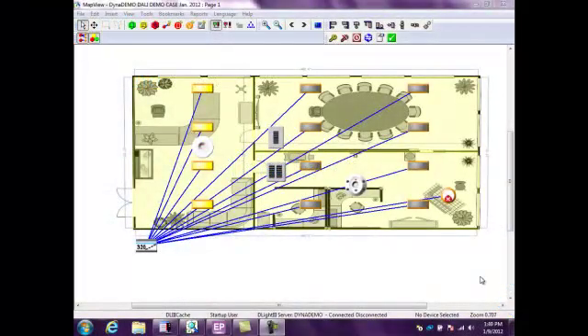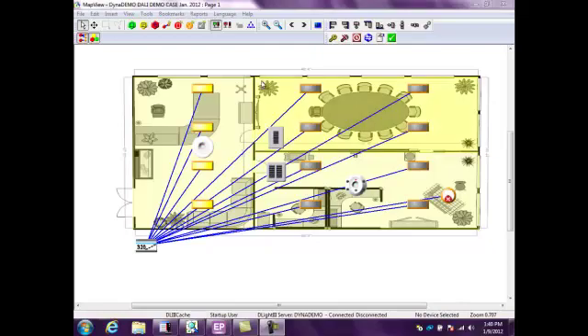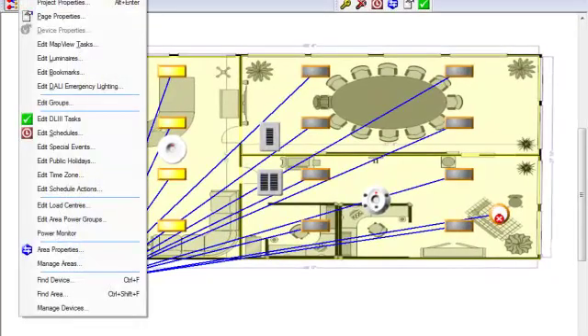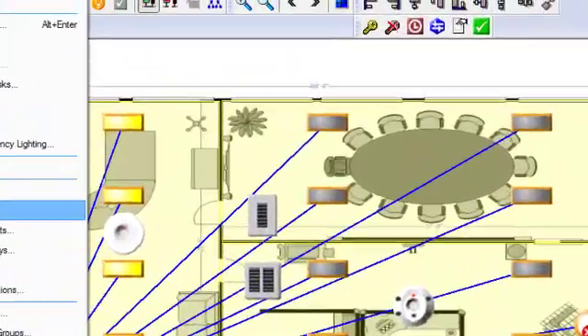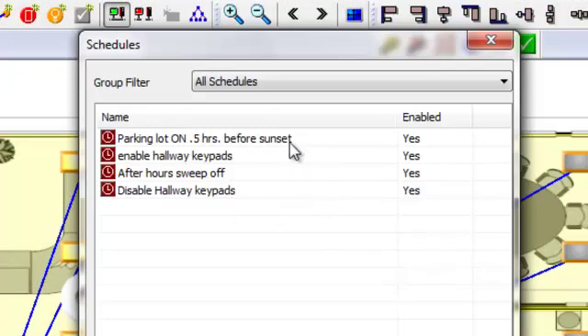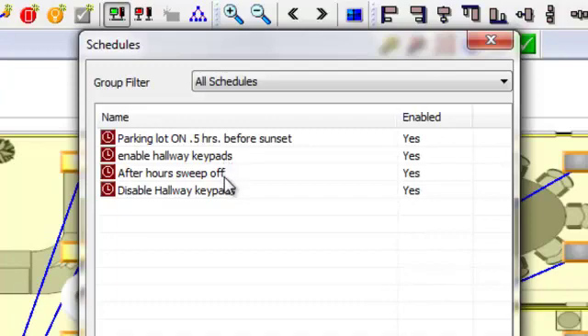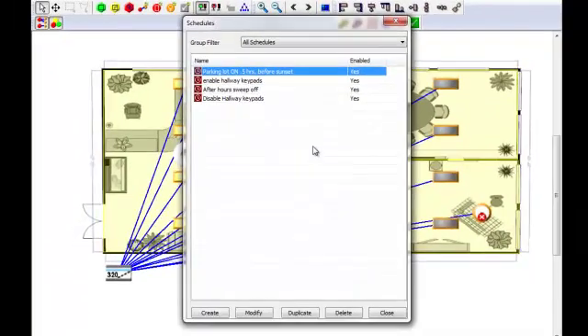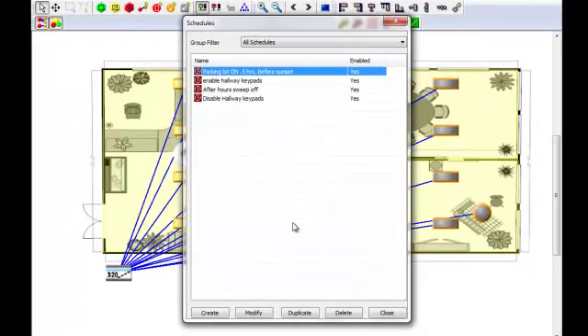We're going to take a second and talk about a timed event. A timed event can be more than just a time sweep to turn lights on and off in a particular area. It can also unlock or lock a keypad, enable or disable sensors, or even send a preset offset so a button press will act differently during a certain time of day. It's very easy to go ahead and adjust these things. You can just go into the edit schedules. You'll see I have a number of these already created. One to enable the hallway keypads. So you're walking through the school, you want to create some mischief and turn the lights off in the class. Well, not with this enabled. You won't be able to create, you won't be able to do anything with those keypads because they are disabled during school hours. After hours sweep off. This is just to make sure that everything's turned off. And disable those hallway keypads. So enable them and disable them. The one we're going to talk about is the actual parking lot on and off.